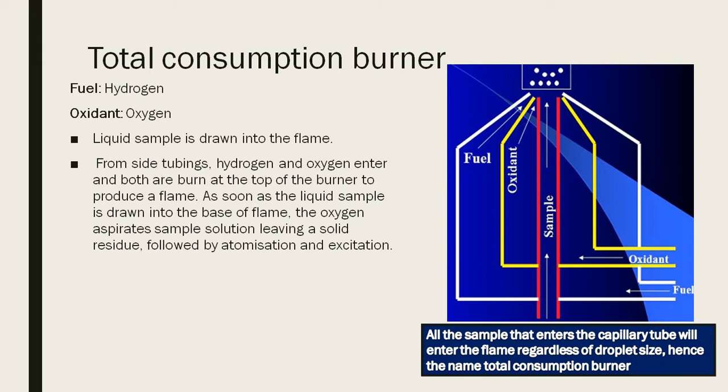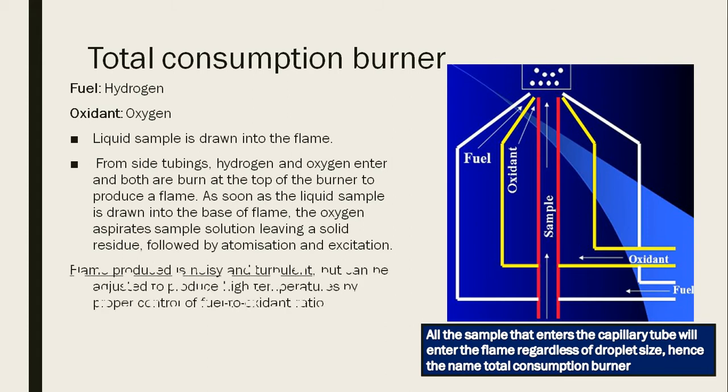As soon as the liquid sample is drawn into the base of the flame, the oxygen aspirates the sample solution, leaving a solid residue followed by atomization and excitation. The flame produced is noisy and turbulent, but this can be adjusted to produce high temperature by proper control of the fuel to oxidant ratio.